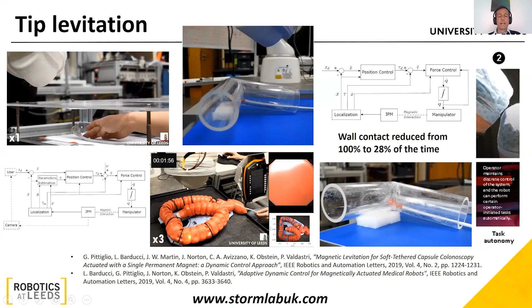Another task that can be automated is ultrasound scanning. Magnetic manipulation always forces the device inside the body to stay in contact with the tissue. And this is ideal when working with ultrasound, where contact with tissue is required to guarantee a proper signal. The challenge, however, is how to control an intracorporeal ultrasound probe to maintain a stable contact during an ultrasound scan, and then how to reconstruct meaningful ultrasound images.